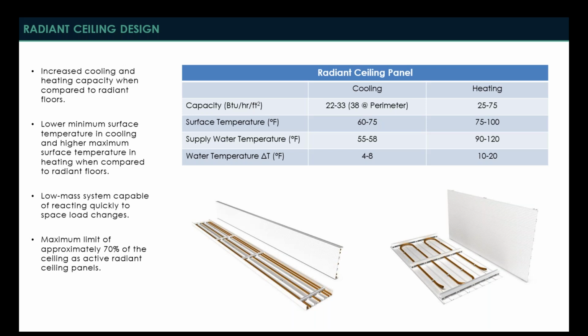The good thing is that for a radiant ceiling panel system, you're essentially using the same elevated chilled water and low hot water temperatures that you're using with the floor system, which is kind of nice because you shouldn't view these systems as something that has to be all or nothing. It doesn't have to be all radiant floor or all radiant ceiling. You can actually combine the two in various portions of buildings where they work the best.